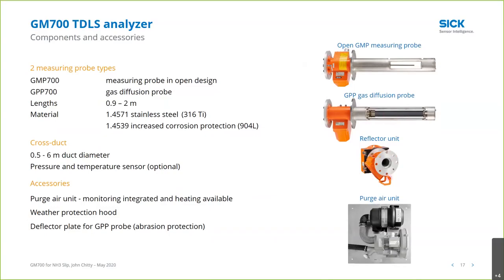And then thirdly, we have the cross duct unit. So we just have the analyzer head on one side of the duct or stack and the reflector unit on the other side. For the cross duct unit, it's good from 0.5 meter to 6 meter duct diameters. However, if it's a dusty application, which a lot of these are, you cannot use the cross duct. We need to stick with one of the probe versions. And the probe versions eliminate things like alignment issues and stuff as well.